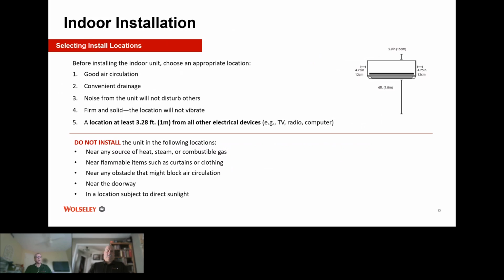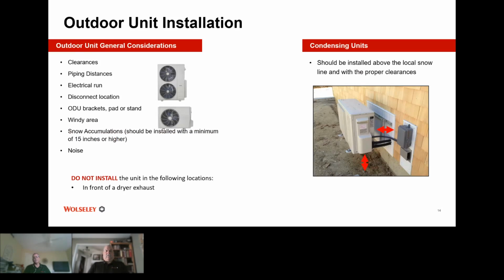Outdoor units, again, clearances, make sure it's far enough away from the building so it has airflow, airflow, airflow. Your piping distances, make sure of your piping distances because manufacturers give you how many feet you can go without having to add refrigerant to the unit. So if you go beyond that, you've got to add refrigerant to make sure you've got enough in the system. And a normal install runs between 8 and 15 feet. That way you don't have to add refrigerant and you keep the noise outside where it belongs. You don't get as much transfer of noise that way.